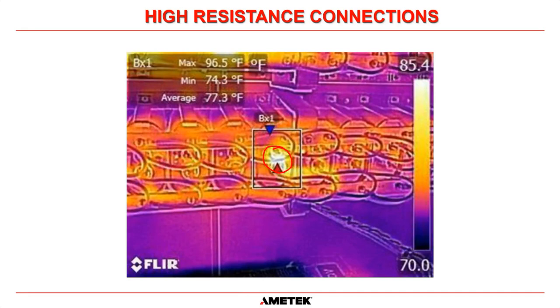So therefore, he powered the system down, performed his maintenance, and when he went in, he found that one of the wires going to this capacitor wasn't connected correctly. It actually wasn't on the spade terminal. It was accidentally pushed on between the spade terminal and the plastic collar that surrounds the two terminal pins. And that was just an accident waiting to happen. If that had been left for a long time, that would have heated up over and over and over again, and it could have led to a fire. So very simple example of how infrared thermal imaging can help you find hotspots with high resistance connections.